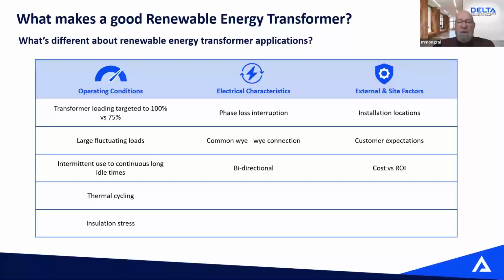There can be some very long idle times: a wind farm if you have no wind, a solar farm if you have no sun. Your transformer will just be sitting there burning no-load losses. So that's different than a standard transformer. There's lots of thermal cycling: idling, small heat rejection from the transformer, then full load, lots of heat rejection. So lots of thermal cycling, expansion and contraction of your coils and the core.